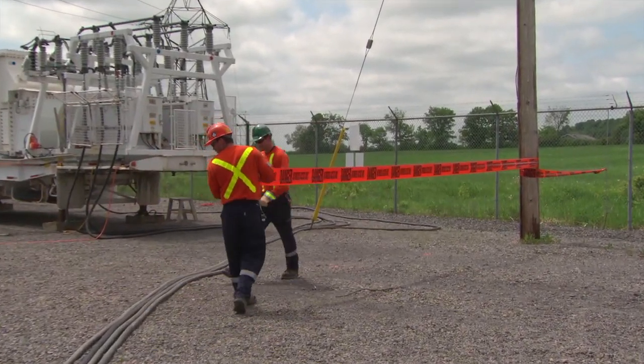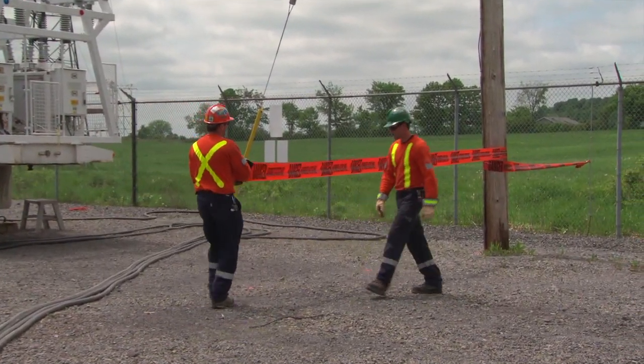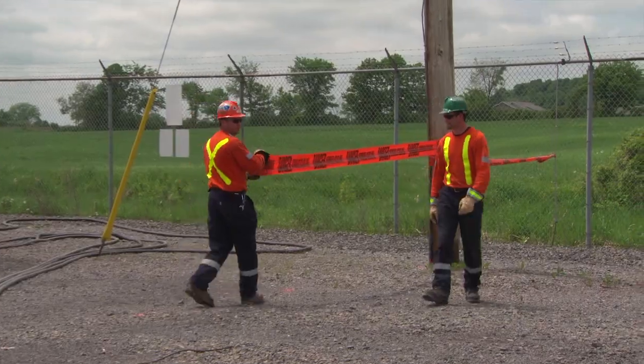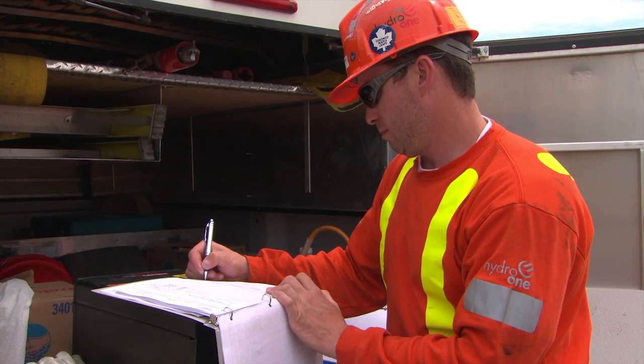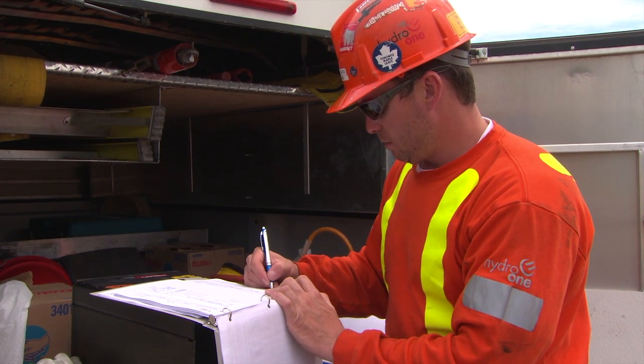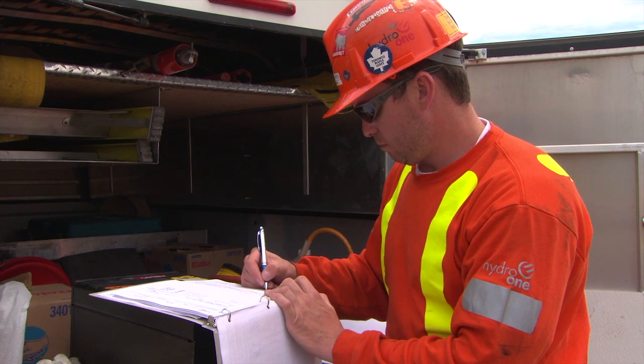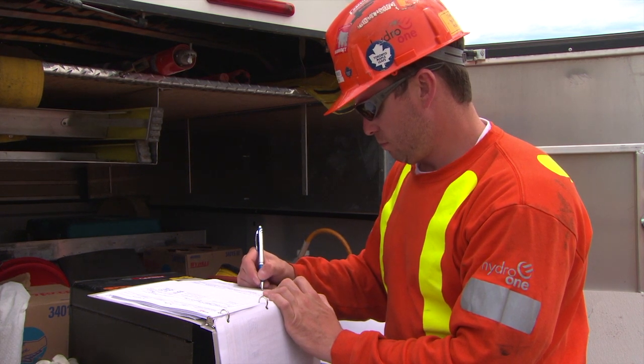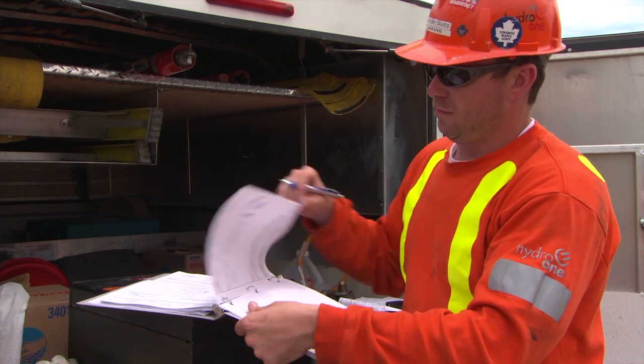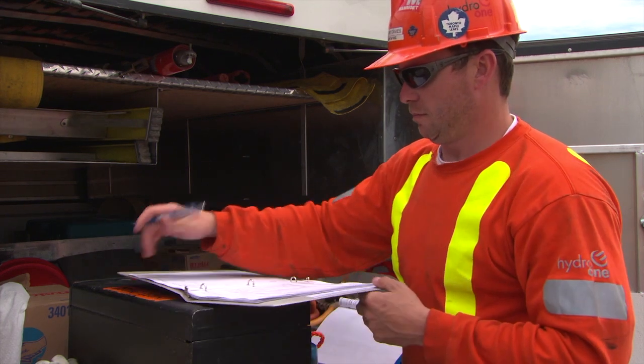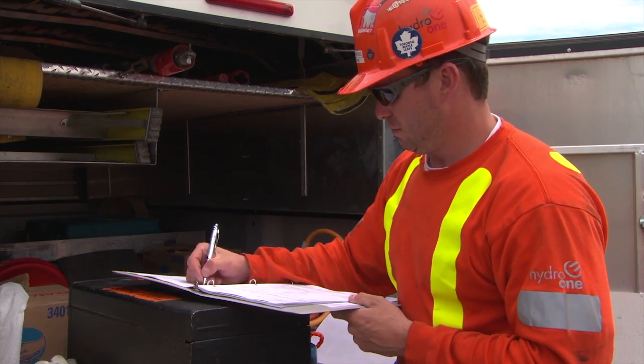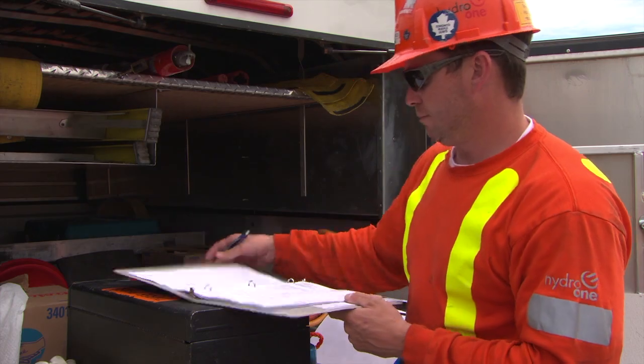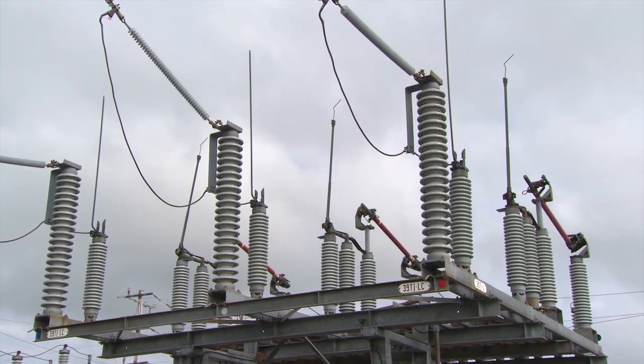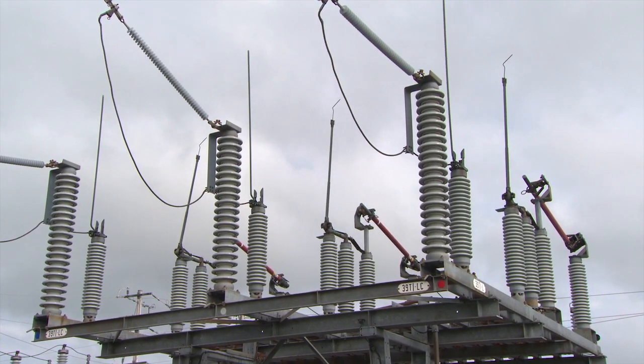Remove barriers to allow easy access to the low-voltage cables and the MUS control cabinet. Prepare and check an OTO for switching the DS into service and the MUS out of service. Obtain a hold-off on the high-voltage 115 kV circuit. This hold-off must remain in effect until the MUS conductors and cables have been disconnected from the DS.